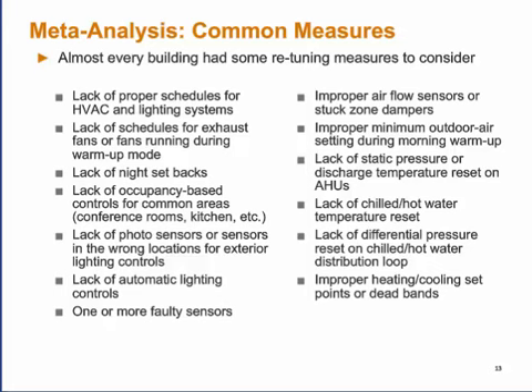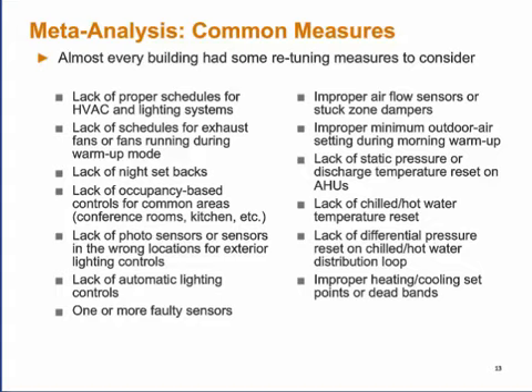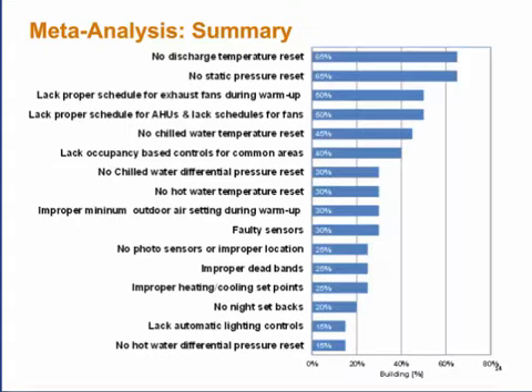Lack of static pressure reset is one of the big savings opportunities—resetting static pressure based on zone conditions. You hardly see that type of control sequence implemented in building automation systems.